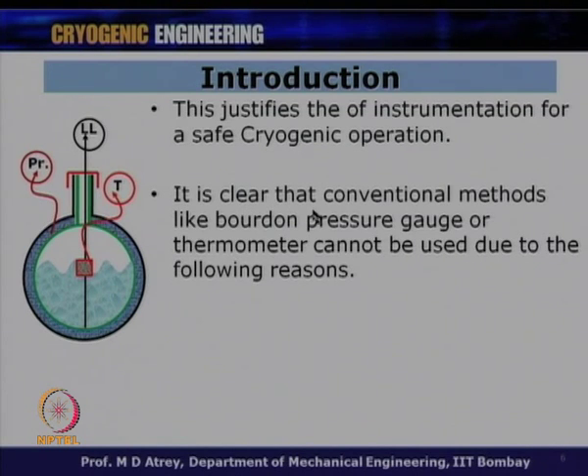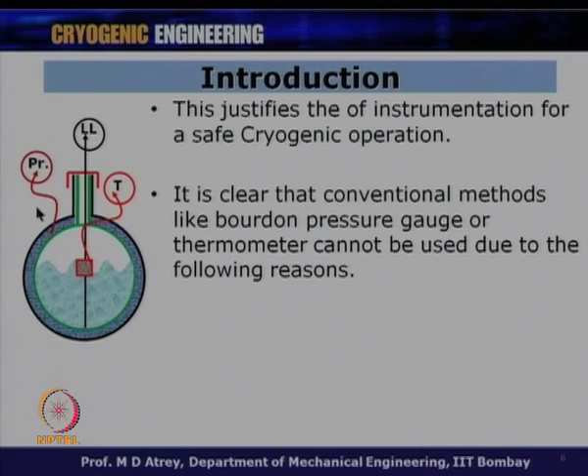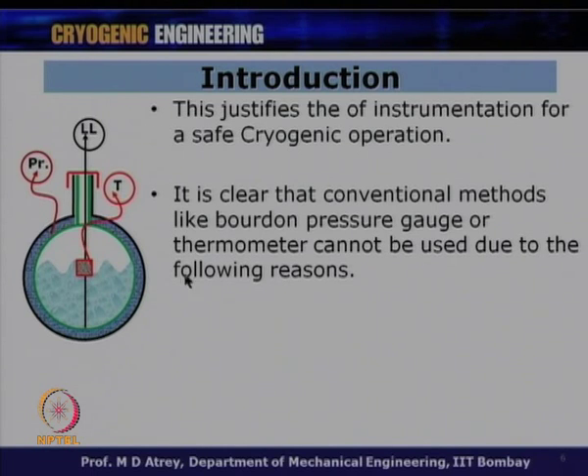Conventional methods like a Bourdon pressure gauge or mercury thermometer cannot be used in cryogenic conditions—a Bourdon gauge cannot measure vacuum (negative pressure), and mercury thermometers cannot work at cryogenic temperatures. Special sensors are needed that will work at very low temperatures and satisfy additional requirements that become more stringent at lower temperatures.